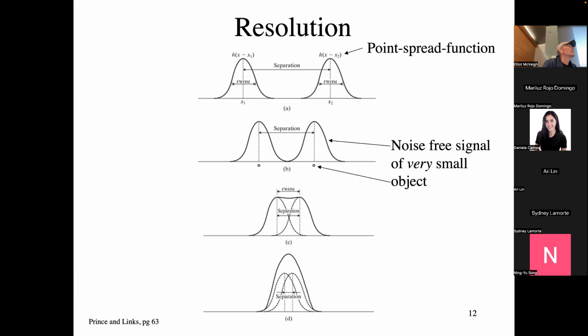So, I was wondering for CT, do you have a lot of control over the resolution? Can the tech actually make it variable? No. In CT, basically the resolution is set by the detector array mostly, and the separation of the detector elements on that array. And then in certain high resolution modes, the spot size of where the X-rays are coming from is important.